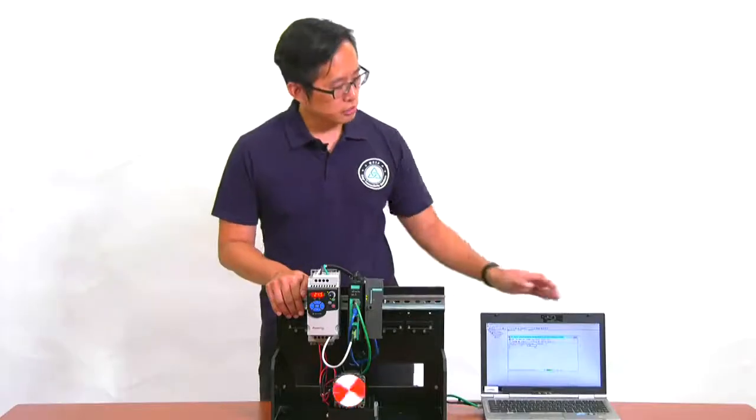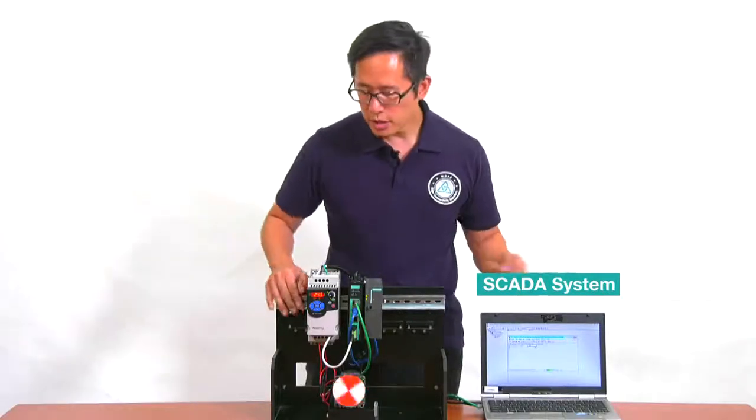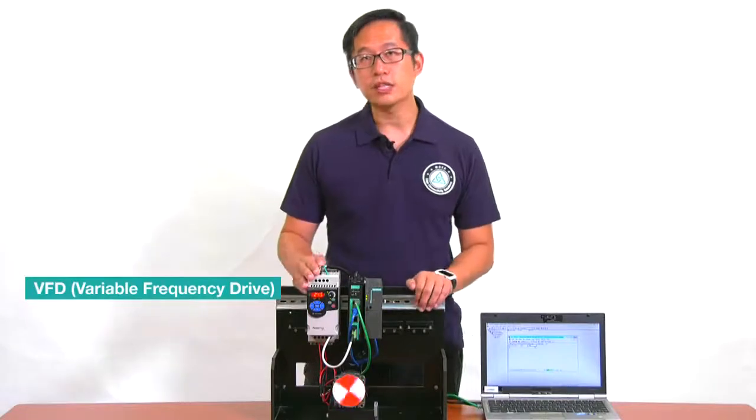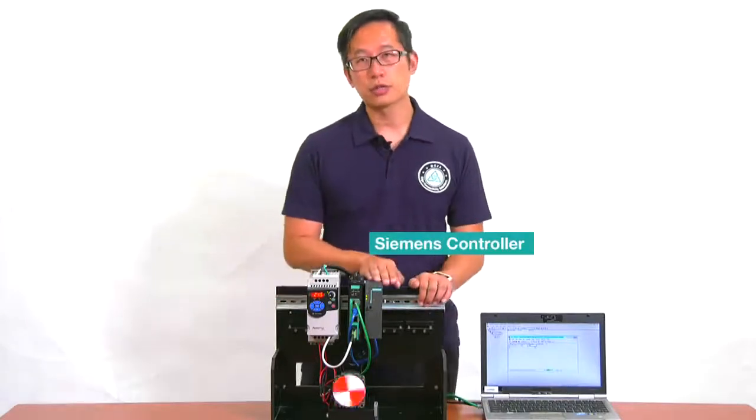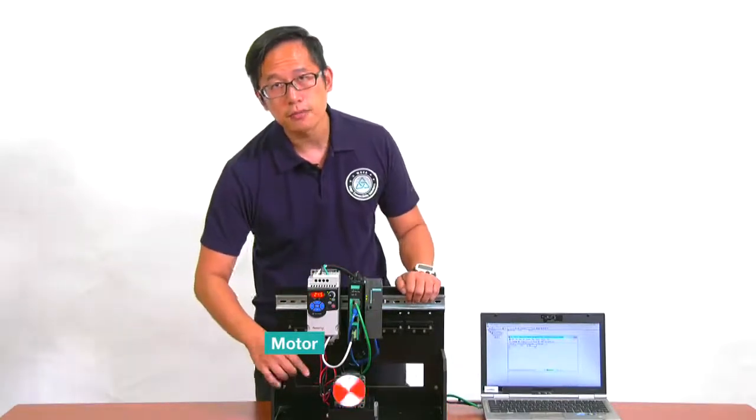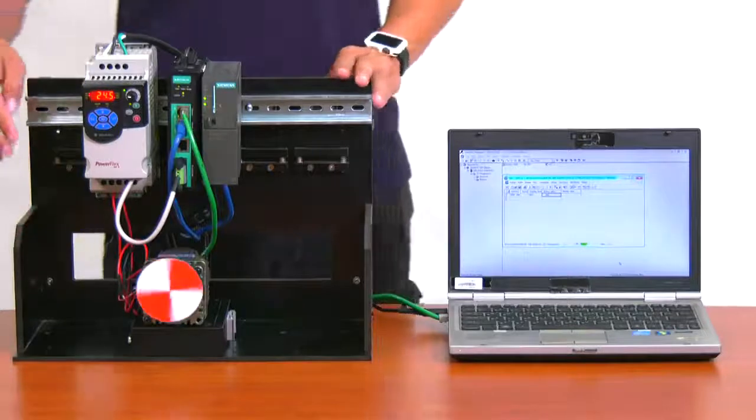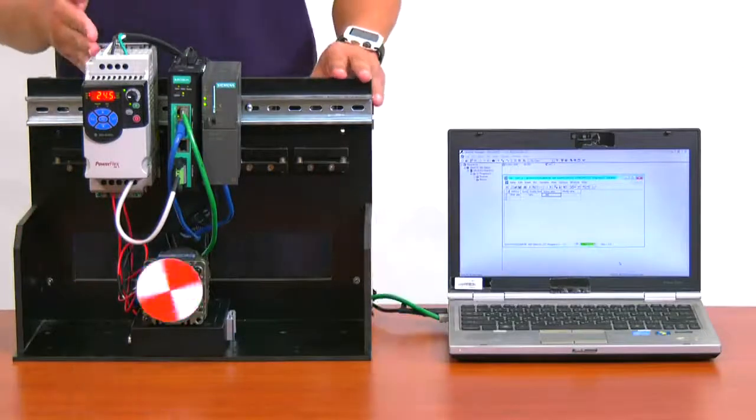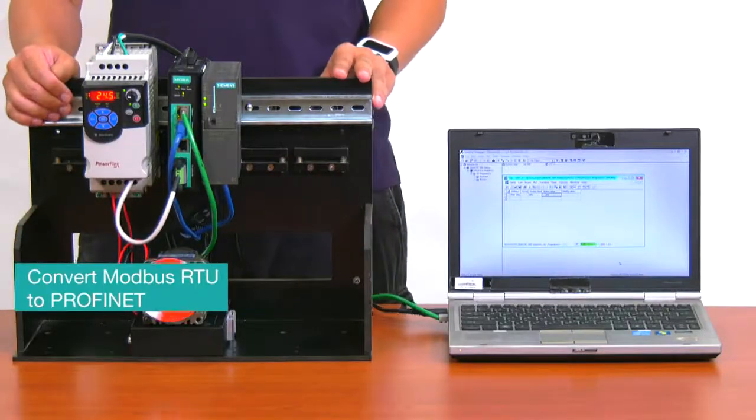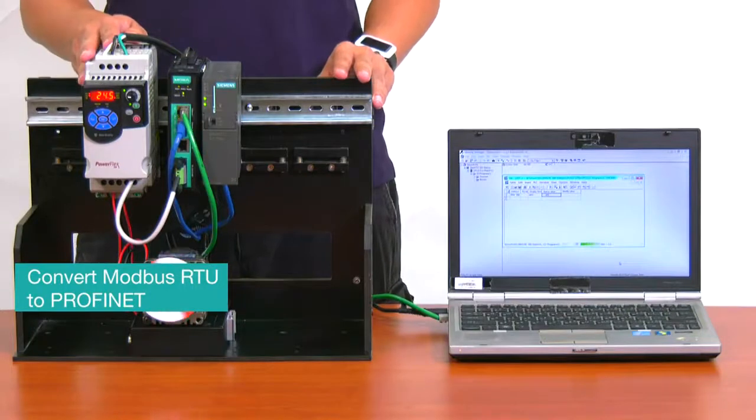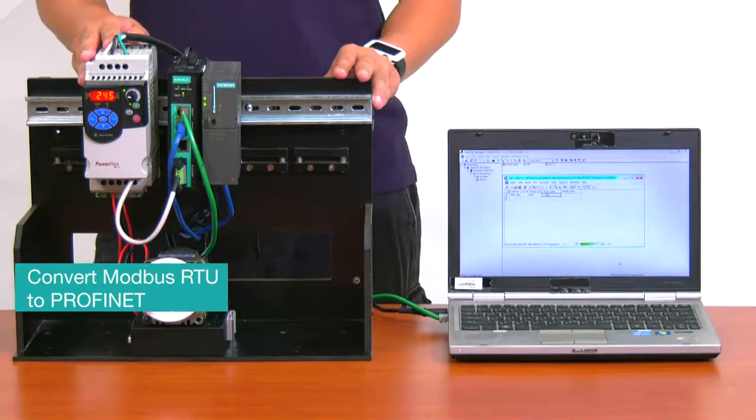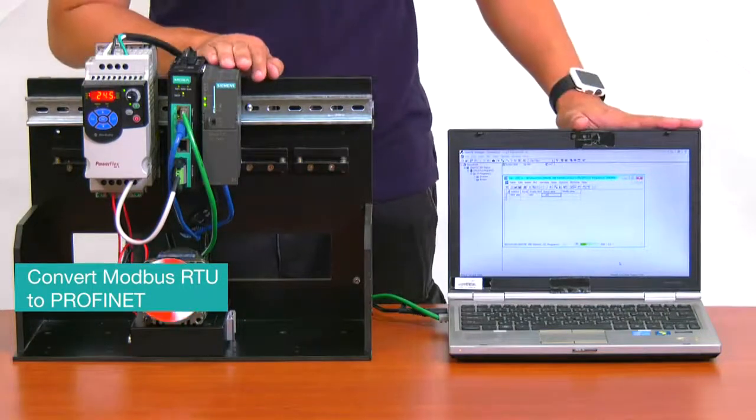Here, we have a PC running SCADA software, and we have a VFD that's connected to a Profinet controller to control the speed of this motor. Now, to connect the VFD to our control network, we have to convert Modbus RTU protocol, which the VFD uses, to Profinet protocol, which the controller and SCADA software use.